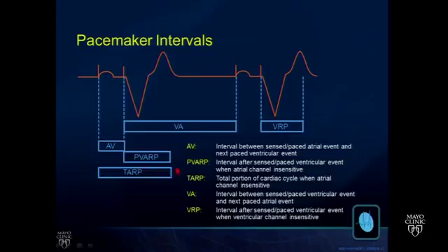As in single-chamber devices, there is a ventricular refractory period that has the objective I mentioned earlier. There is also something I will introduce to you called the post-ventricular atrial refractory period, an interval after a ventricular paced or sensed event when the device will not respond to an event in the atrial chamber of the device, so that a P wave occurring during this time frame will not be tracked by the device. And this PVARP exists to prevent inappropriate tracking of such things as the T wave. It also exists to prevent an entity called pacemaker-mediated tachycardia, which I'll review for you in just a moment.